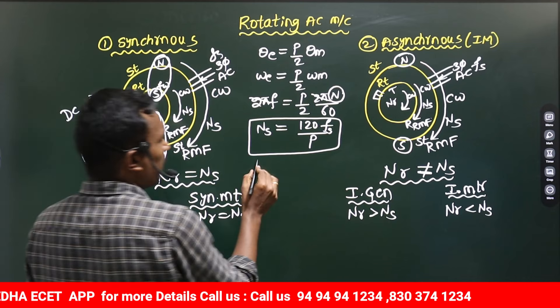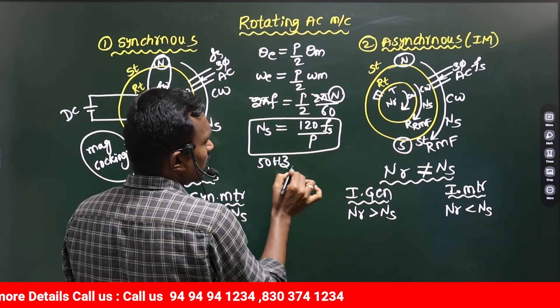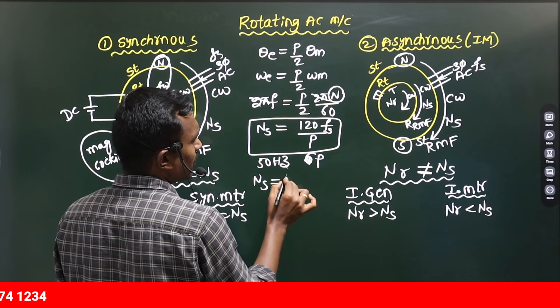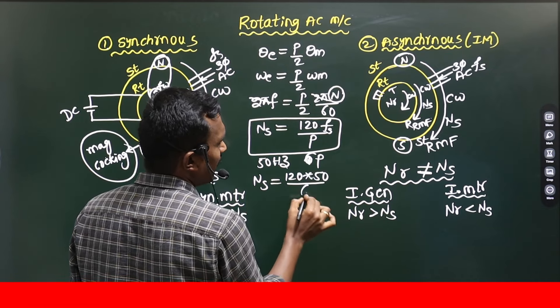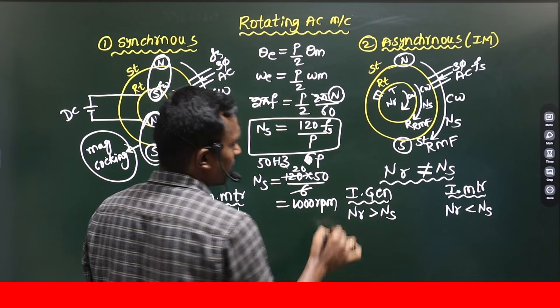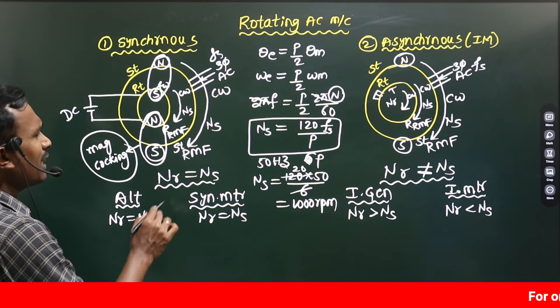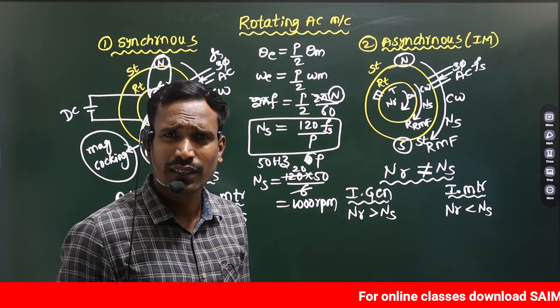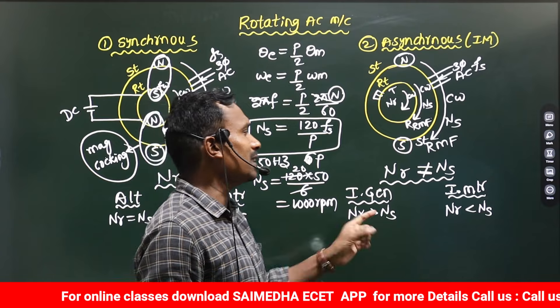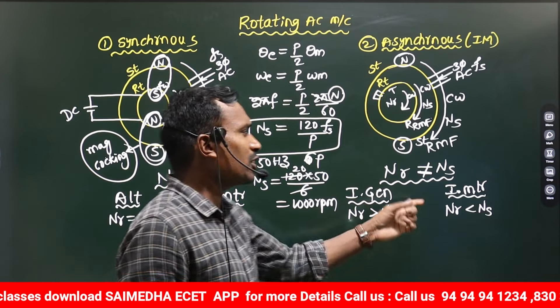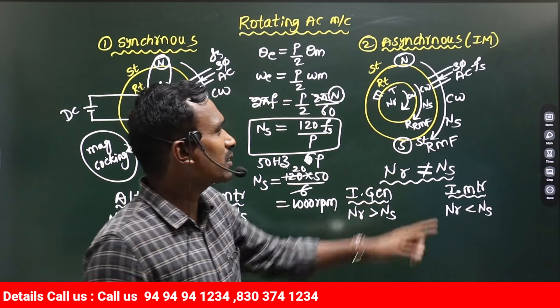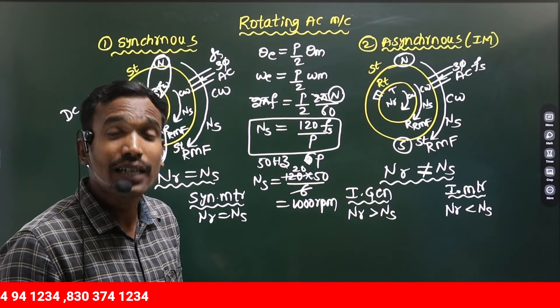For example, for a 50 Hz machine with 6 poles, the Synchronous speed Ns = 120 × 50 / 6 = 1000 RPM. If the rotor rotates at 1000 RPM, that is a Synchronous machine. If the rotor rotates at slightly more than 1000 RPM, that machine is called an Induction generator. If it rotates at slightly less than 1000 RPM — for example, 970 RPM — that is called an Induction motor.